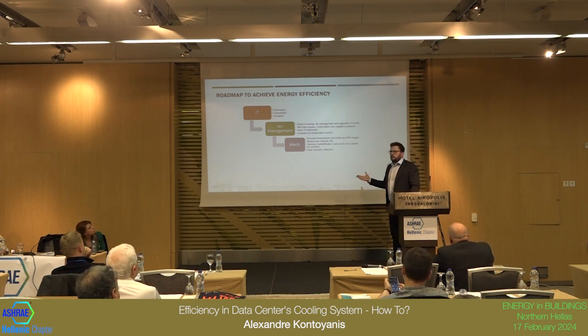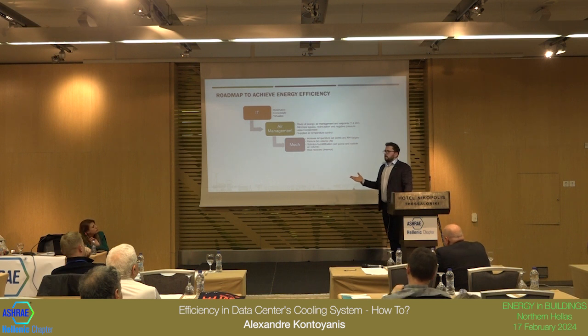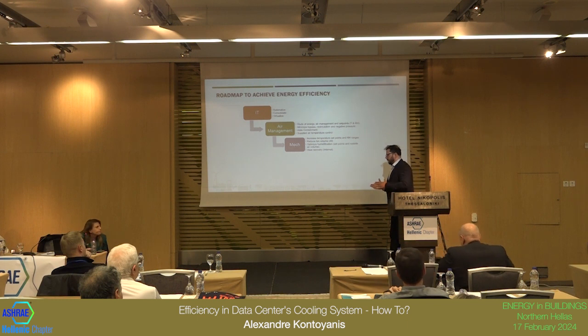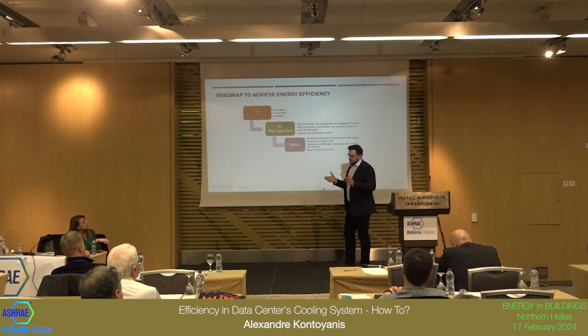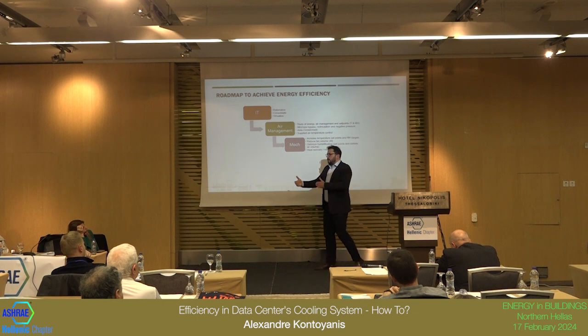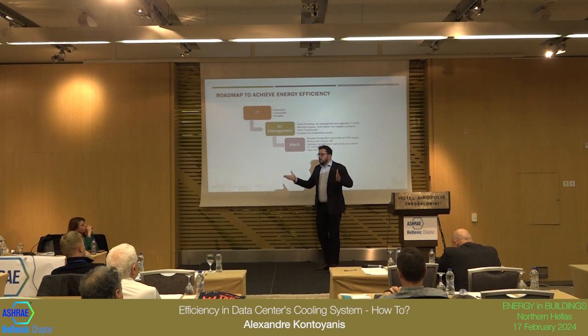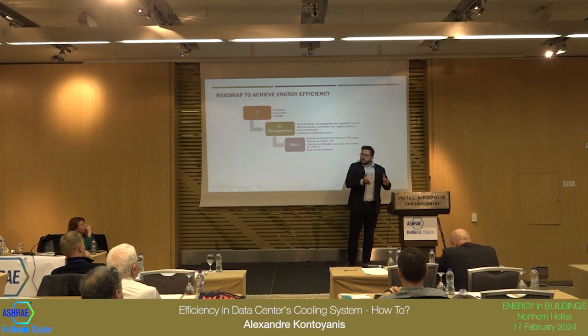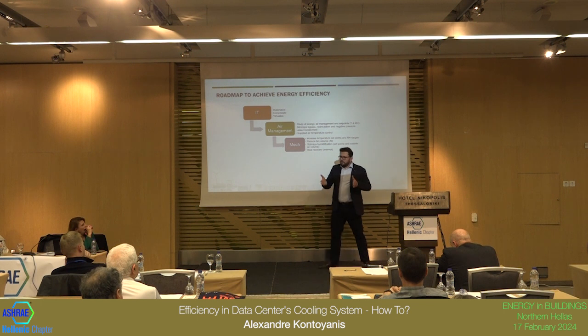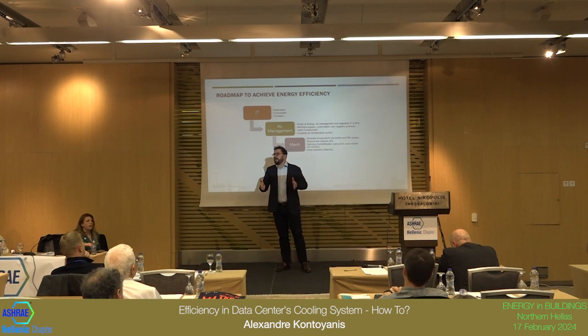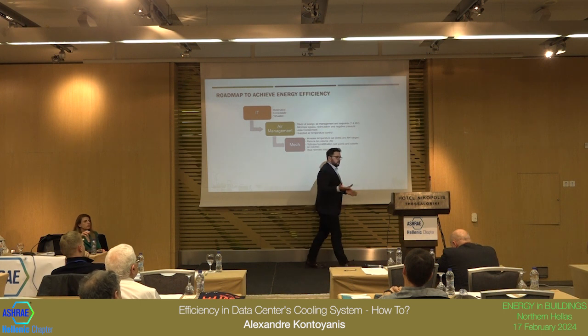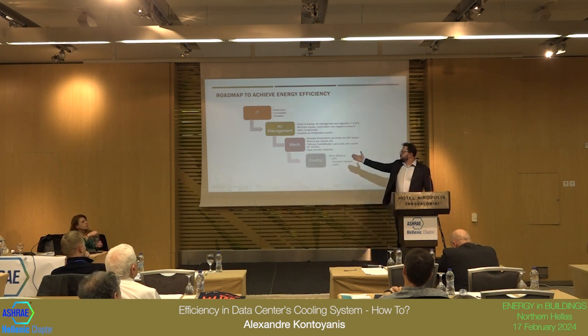can use heat recovery. You have air at a temperature of 60 degrees. I saw in Argentina one data center where the return temperature is around 40 degrees, and the winter in Argentina is cold. And they have the office, the place where the people work, and they heat it with gas. You have a room here rejecting air at 40 degrees, and you are heating this room with gas. This is just insane.